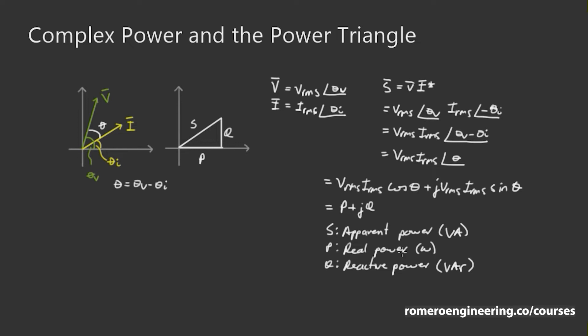You might wonder why we have three types of power. The significance is that S, the apparent power, gives us an indication of how much equipment is going to be heated. Because of that, most equipment in power systems — like transformers, transmission lines, and generators — is rated in apparent power. For example, a transformer might have a rating of 2 MVA, or 2 megavolt-amperes, because that indicates how much heating the transformer can handle.